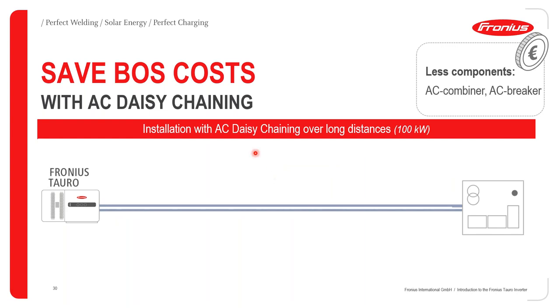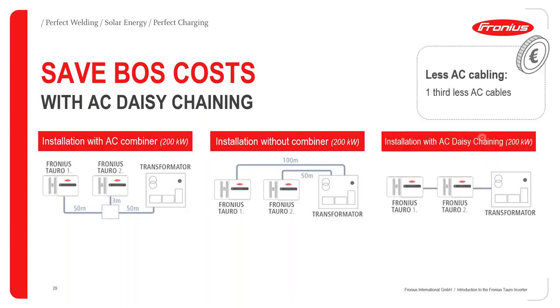So in this particular case, we also look at an installation with the Fronius Tauro with AC daisy chaining for the same power block, which is 200 kilowatts. And therefore, we can see that we are going to achieve much shorter cable distances. If you look at this installation without a combiner box, we can talk about 150 meters of cabling that you require. When you talk about the first example with an AC combiner box, the cable distance is slightly shorter than without a combiner box.